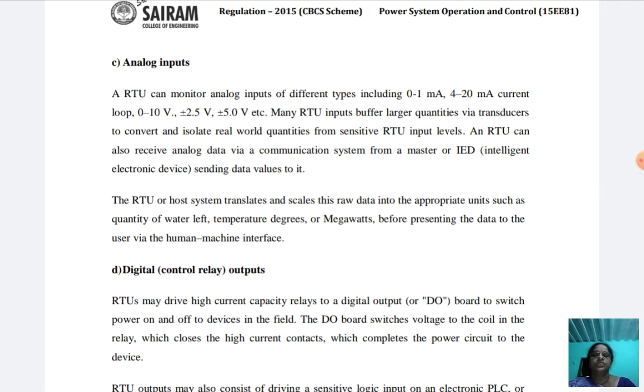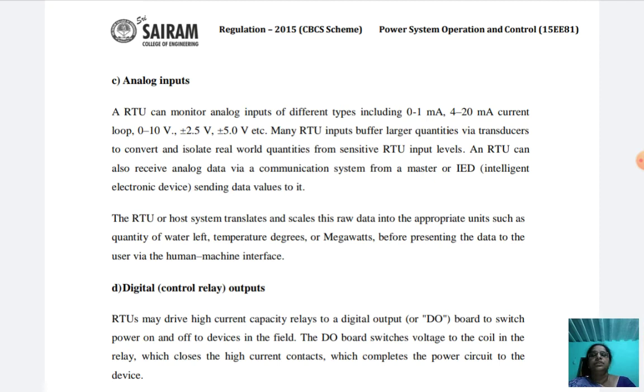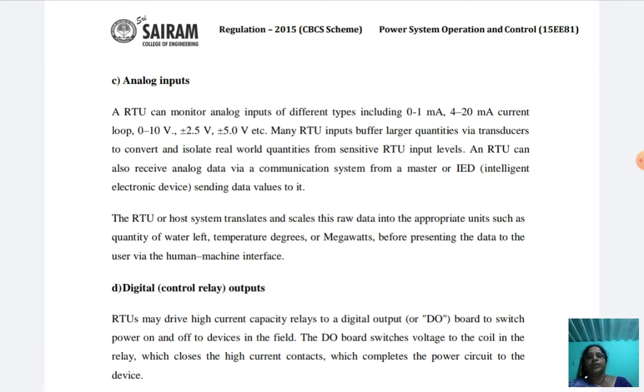The next component is analog inputs. The analog inputs are of different types including 0 to 1 milliamps and 4 to 20 milliamps current loop. Many RTU inputs buffer larger quantities via transducers to convert and isolate real-world quantities from sensitive RTU input levels. The RTU can receive analog data via a communication system from a master or intelligent electronic device (IED) sending data values to it. The RTU translates and scales this raw data into appropriate units such as quantity of water, temperature in degrees, or megawatts.